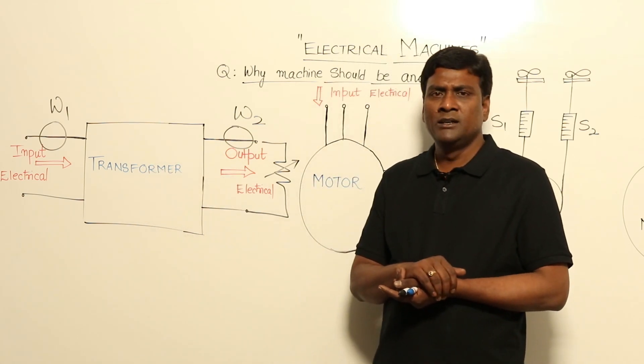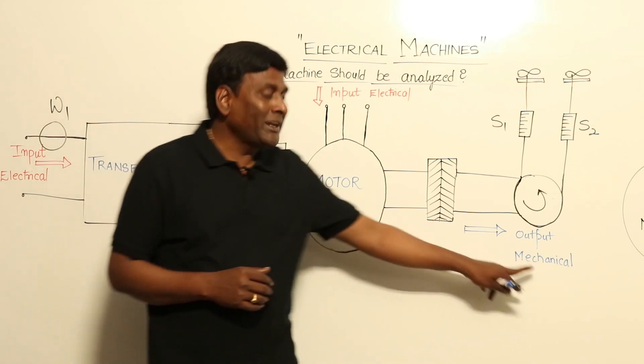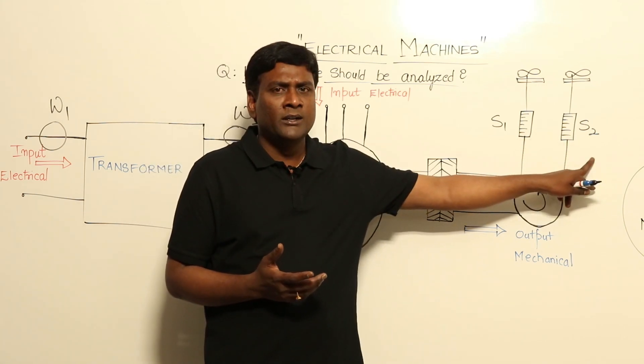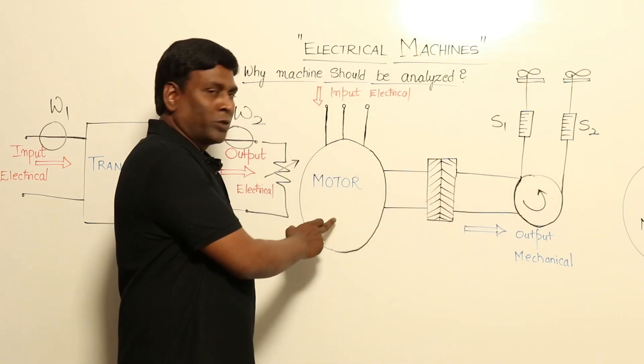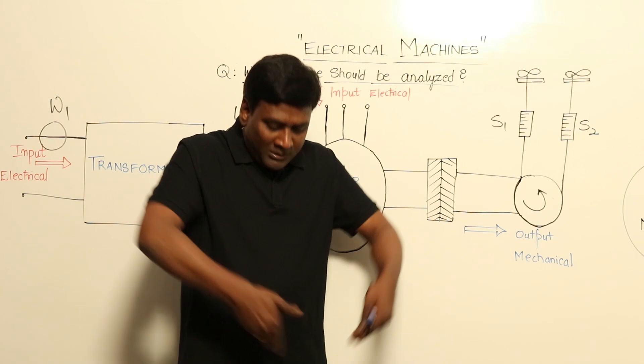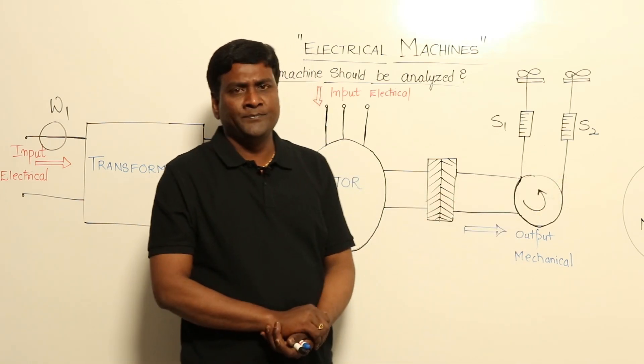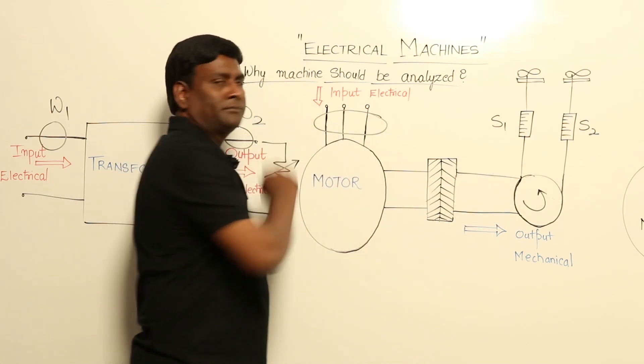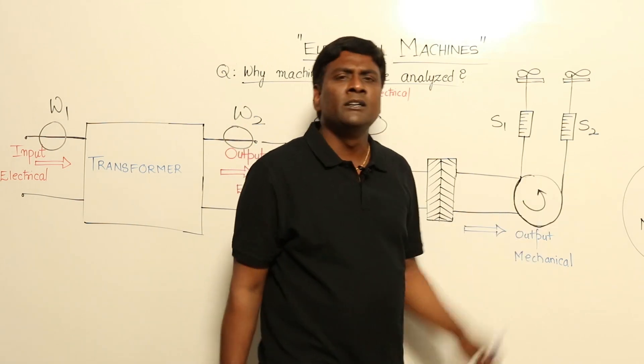In the case of a motor, input is electrical and output is mechanical. The mechanical output power is calculated as (S1 − S2) × 2πN/60 × 9.81, which gives the output power. Connect a brake drum to the motor shaft, attach belts, and tighten them to measure output power mechanically. Input power is measured by connecting wattmeters. So output power divided by input power gives efficiency, and the same approach applies to a generator.